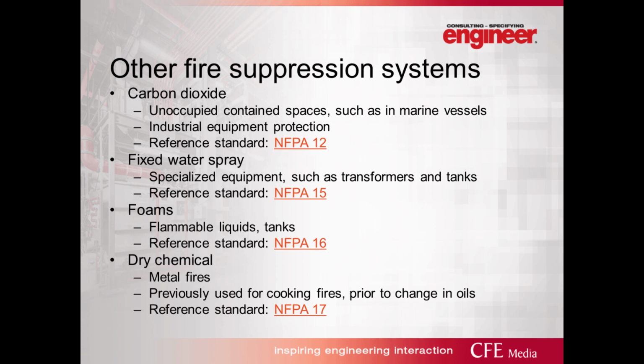Other fire suppression systems that are available: carbon dioxide systems, which are typically used in unoccupied spaces because carbon dioxide does not deal well with occupants in the room. The reference standard for carbon dioxide systems is NFPA 12. Fixed water spray systems are very similar to sprinkler systems, but they use specific nozzles to spray the area of the hazard, typically used on transformers and tanks, and the intent is to cool those transformers and tanks if a fire occurs, not necessarily suppress a fire.